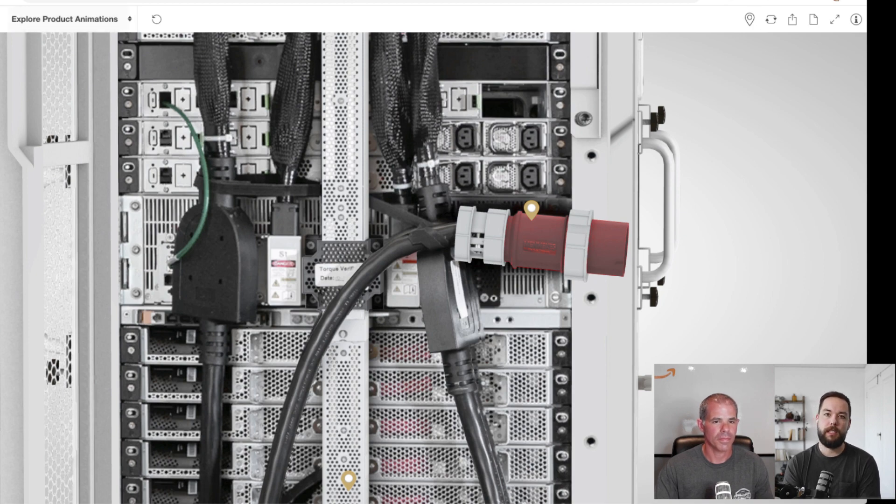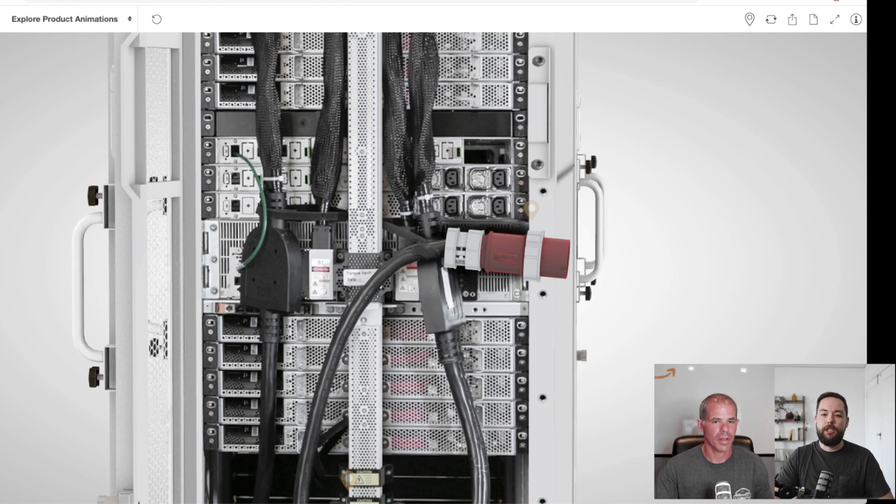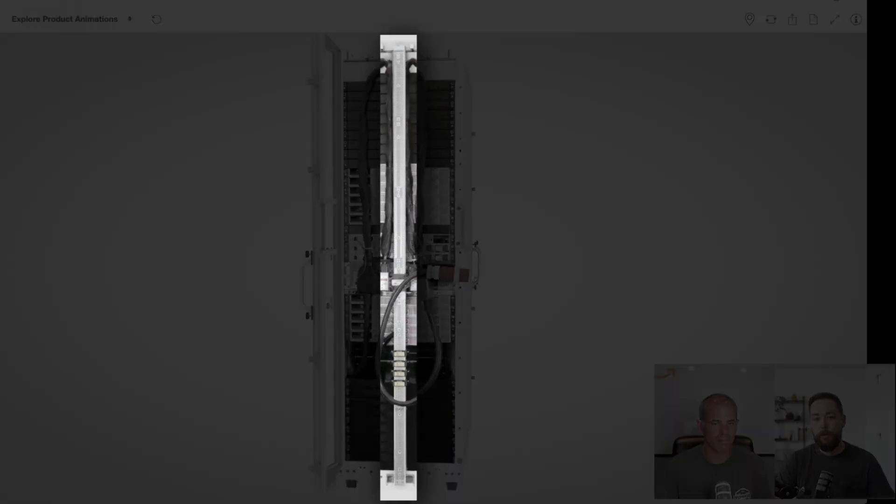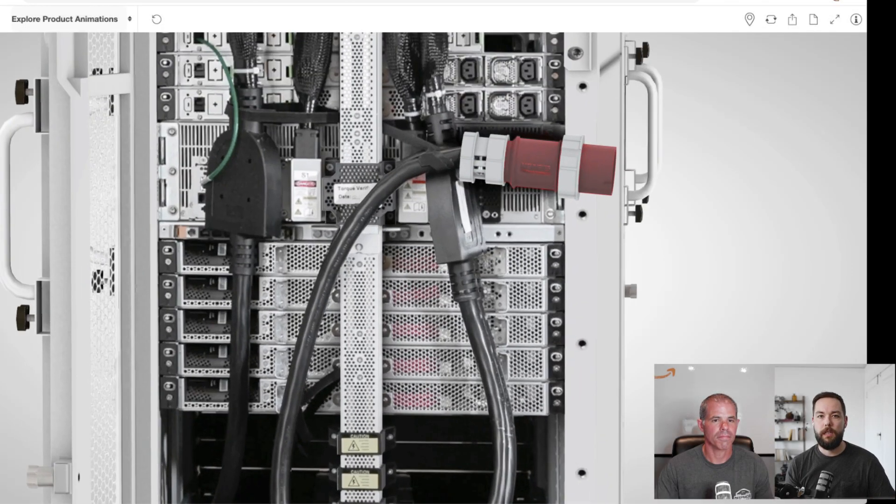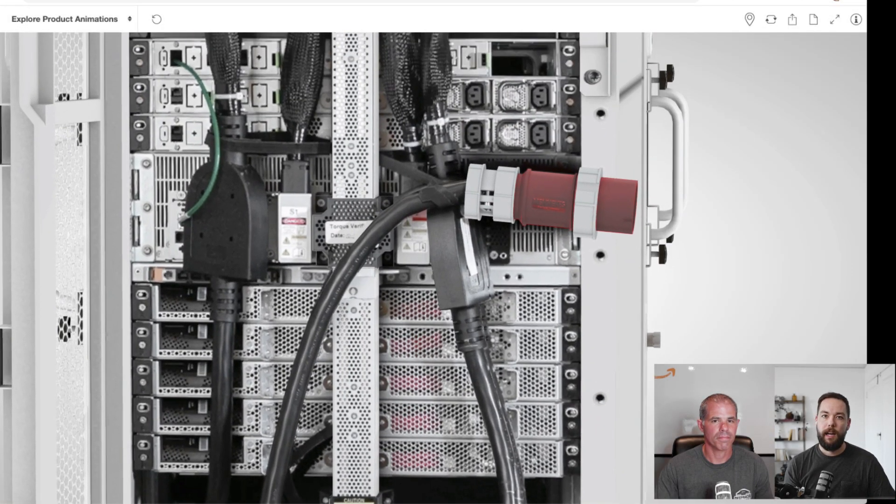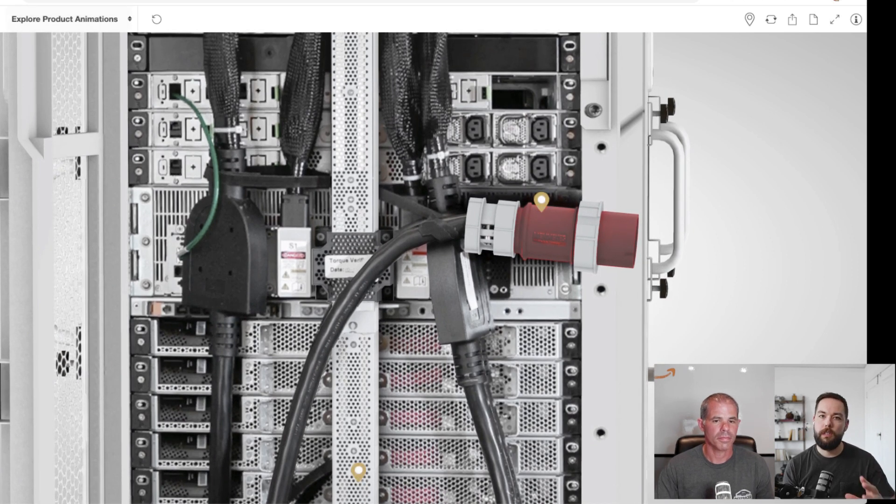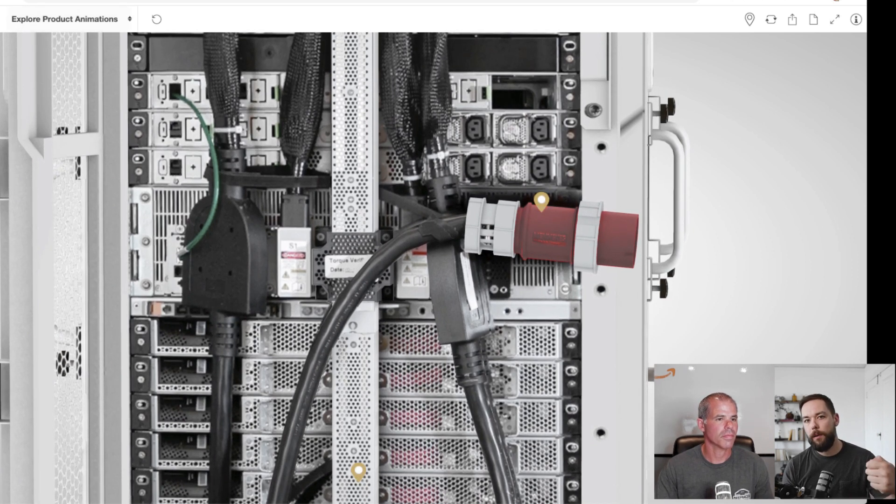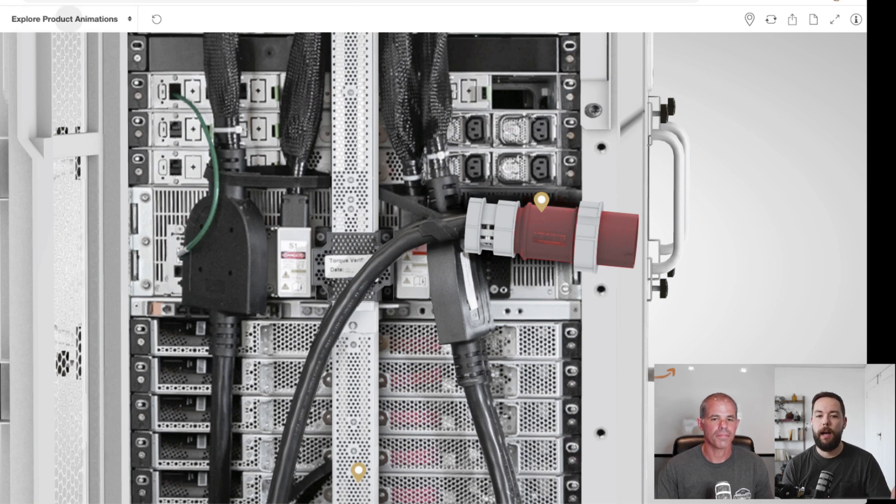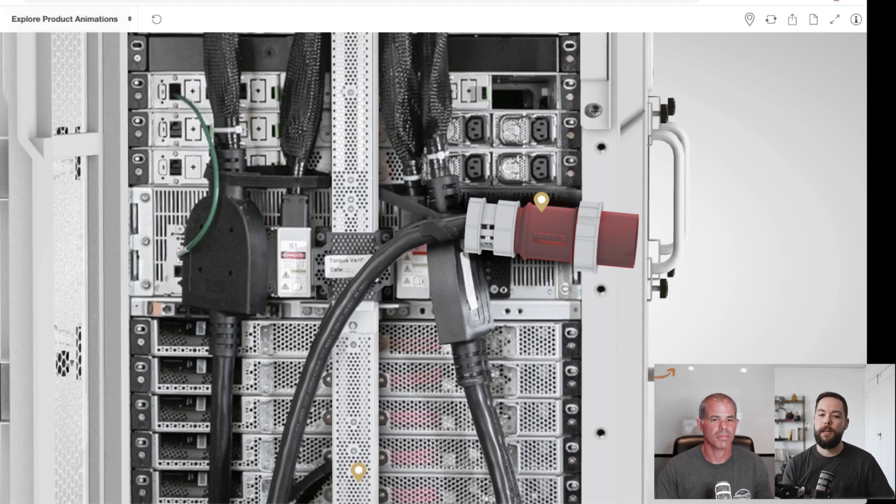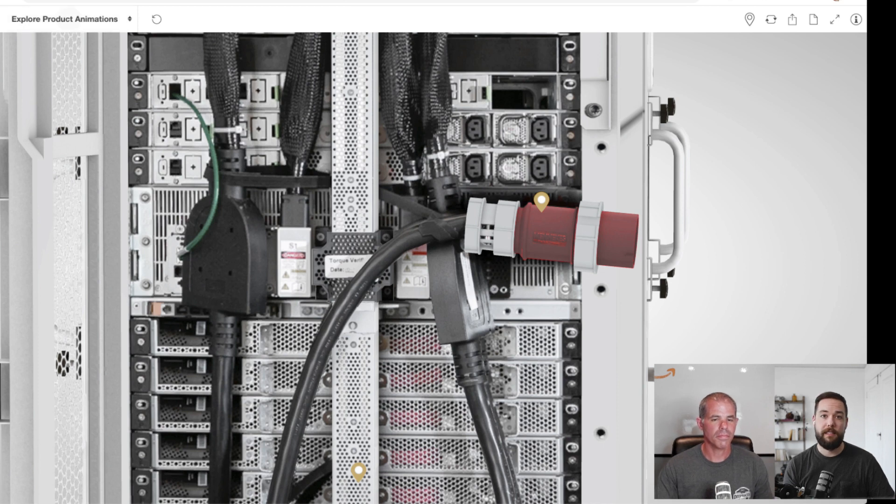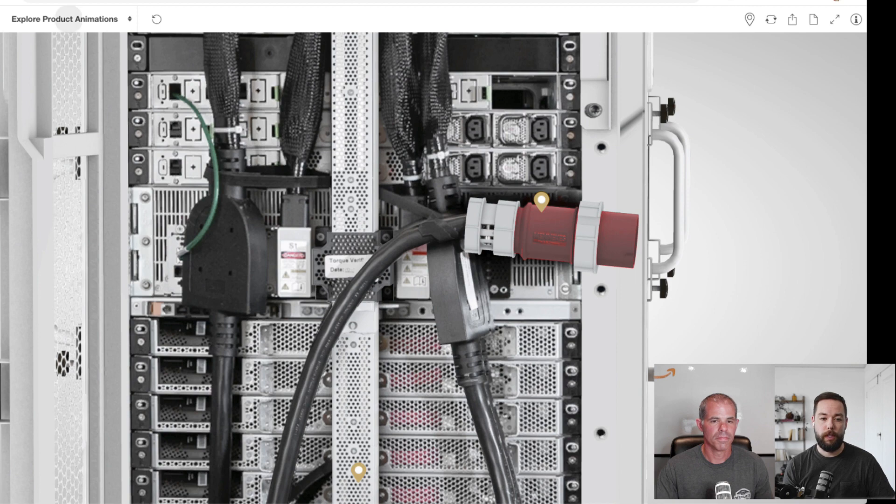But that bar that you see in the center of the rack is actually what we call the bus bar. And so the bus bar is what's feeding the power to the components inside. It's a little bit different compared to when you're actually building a singular rack. You know, let's say you're in a data center and you're putting a whole bunch of hosts in a rack. You'll plug in a power cable into the back of each server. In this case, the bus bar and we've got the power unit in the center there is basically providing power to all of these servers. So it's actually pretty awesome stuff. Something that was different that I hadn't seen before, having worked in data centers and that sort of thing.